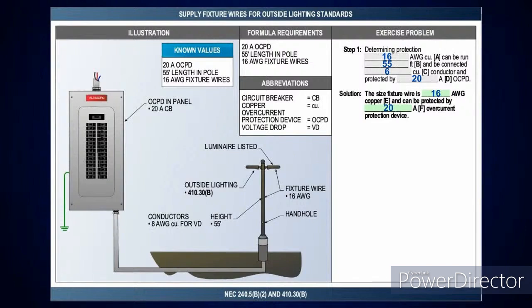Well, the reason I'd have number 6 conductors going over is because I'm calculating for voltage drop. Right. Okay. And what we were trying to point out here is, you get a question like this and you see something where it says connect the number 6 conductors, and you're thinking, why the hell are number 6 conductors going over? Well, this is why: they're having to increase the size of conductors going over due to voltage drop and connecting it to a 20 amp overcurrent protection device.